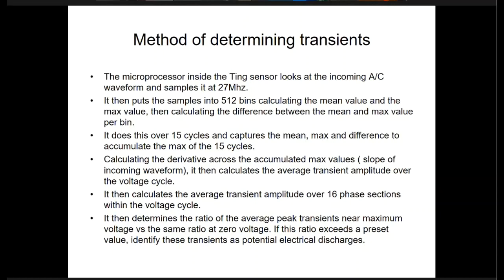Then it does a derivative across the accumulated max values, which is basically the slope of the incoming waveform, and calculates the average transient amplitude over the voltage cycle. It then calculates the average transient amplitude over 16 different phase sections within the voltage cycle, breaking the cycle into 16 pieces to see what the average transient was in each place. It then determines the ratio of the average peak transient near maximum voltage versus that same ratio at 0 voltage, and if it exceeds a preset value, it identifies these transients as potential electrical discharges.